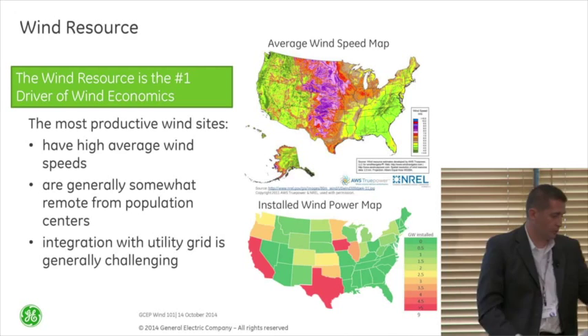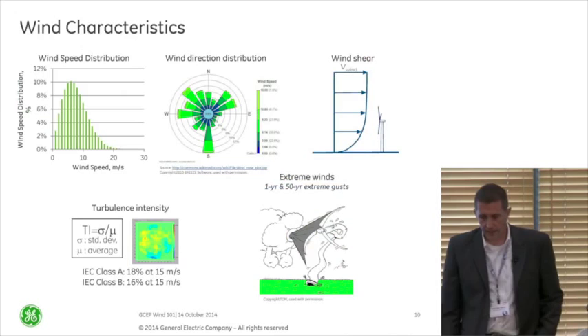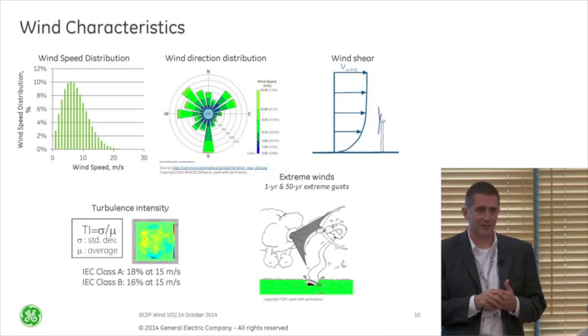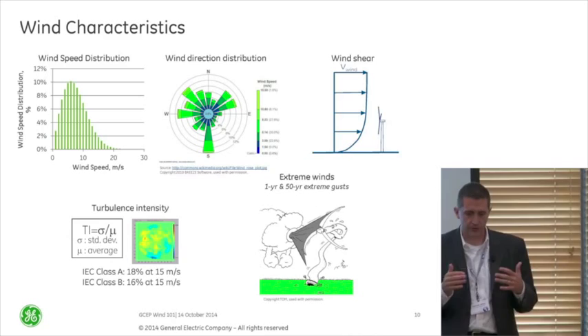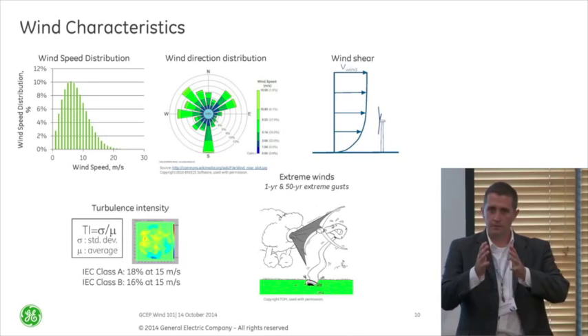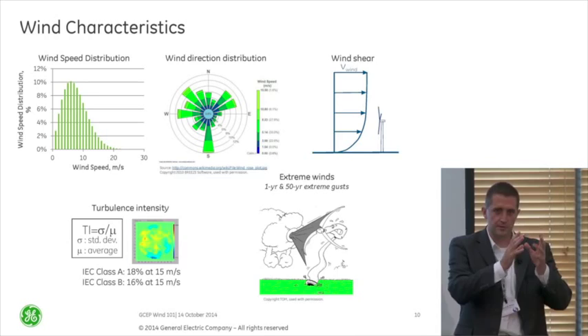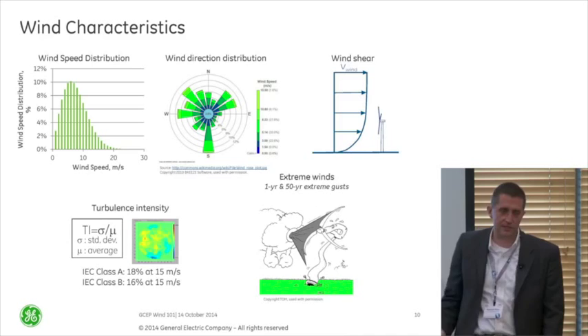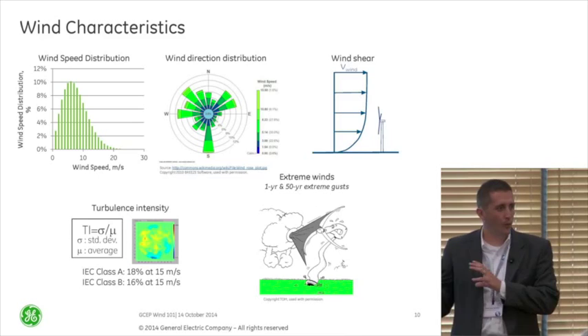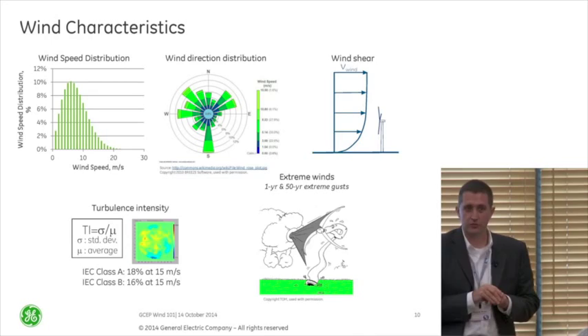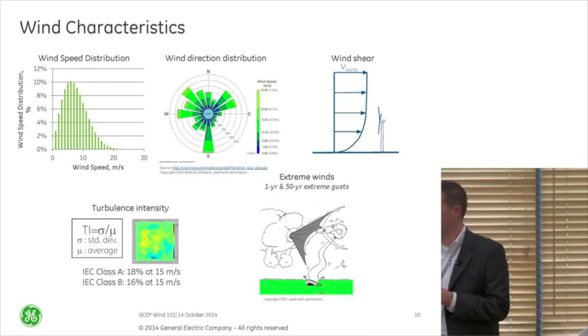To characterize wind, it's not as simple as just using the average wind speed. We actually look at how the wind is distributed — we bin it into one meter per second bins and look at the average time within each bin. You can see a nice distribution called a Weibull type distribution, which is typically what you'd see if you went to a site and measured it. There's also the directional component — often mostly unidirectional, but with different directional changes in where the wind is coming from.